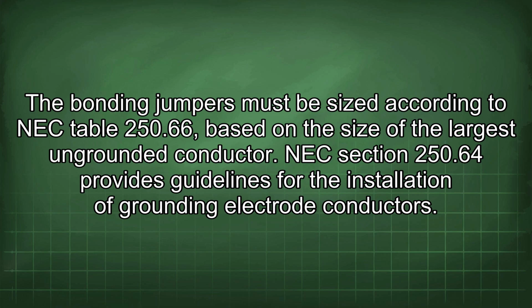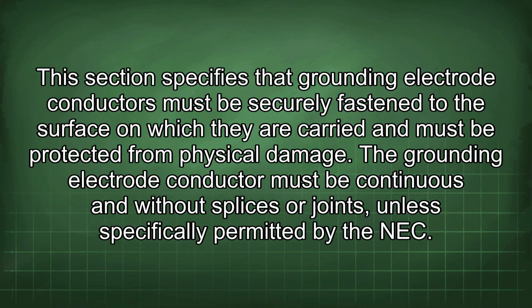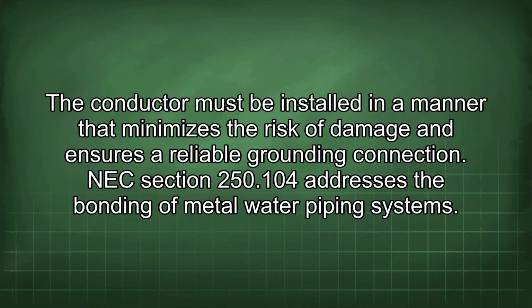NEC section 250.64 provides guidelines for the installation of grounding electrode conductors. This section specifies that grounding electrode conductors must be securely fastened to the surface on which they are carried and must be protected from physical damage. The grounding electrode conductor must be continuous and without splices or joints unless specifically permitted by the NEC. The conductor must be installed in a manner that minimizes the risk of damage and ensures a reliable grounding connection.